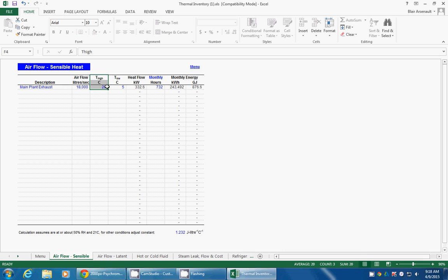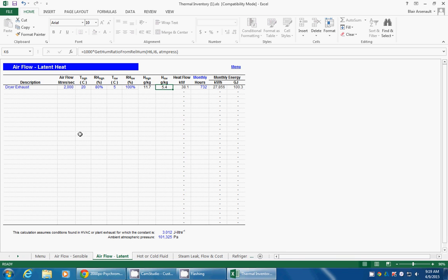So this relative humidity is going to be lower than this relative humidity. But it's that old formula, Q equals 1.08 times CFM times delta T. That's what this formula is, the sensible flow, and this is what we used last year when we were doing all that ductwork stuff. But when we get into dehumidification or air conditioning, we need to factor in that latent heat piece.